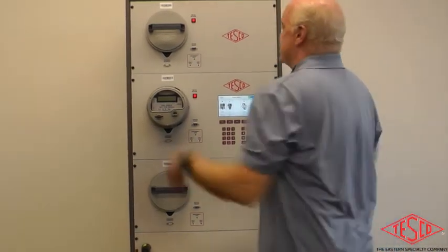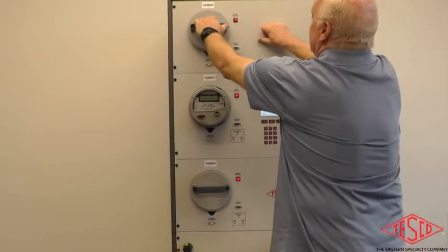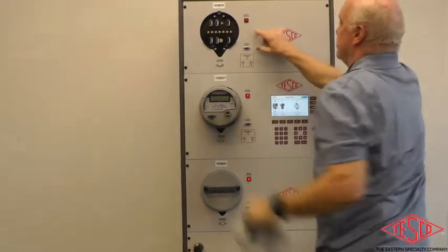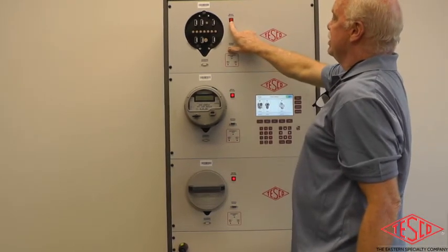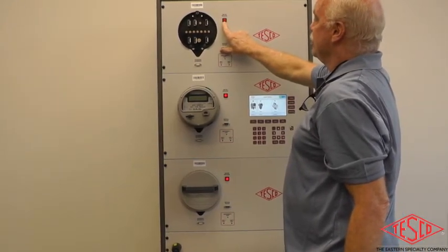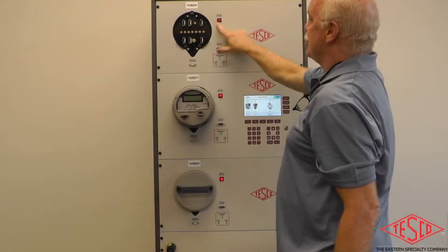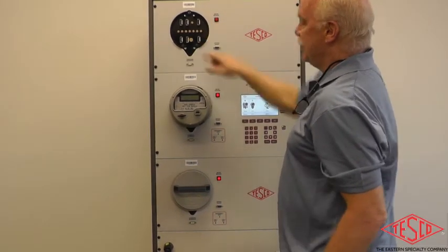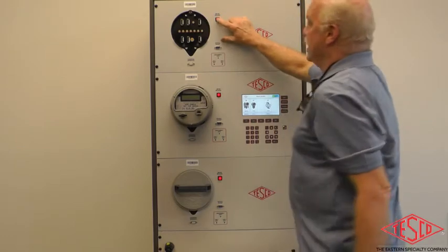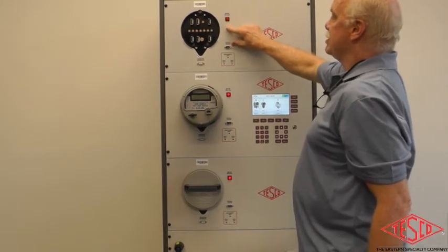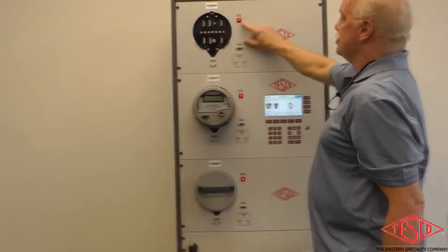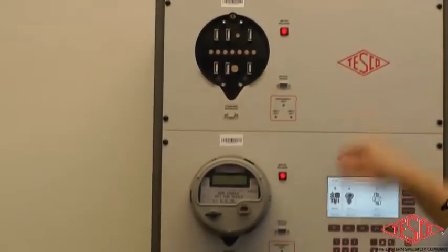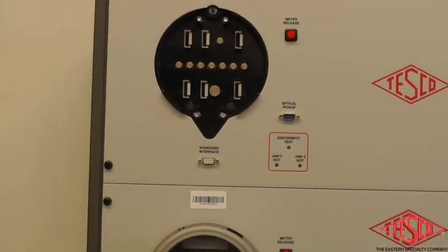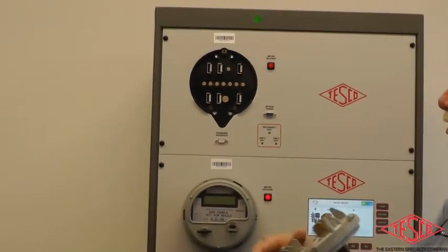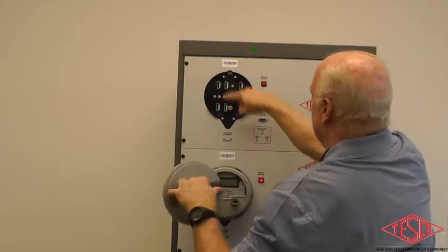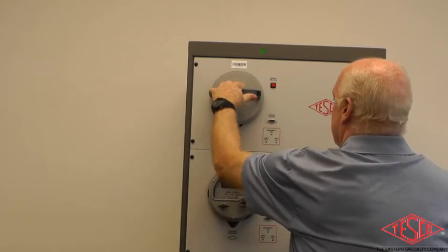I'll talk briefly about the sockets, which are motor driven and basically mostly automatic. You have a meter release and meter insertion button here. Right now, with no meter installed, the light is out and the jaws are open. So it can operate manually by pressing a button. You can see the jaws close, but it also has automatic detection: when you put a bypass or a meter in and it depresses the sensing buttons here, it will close automatically.